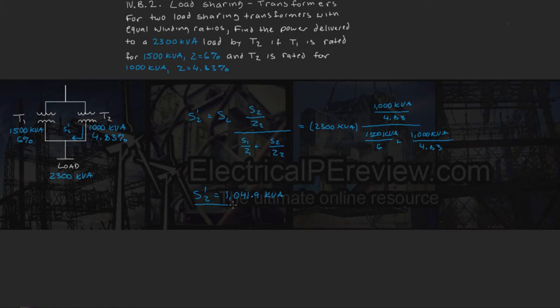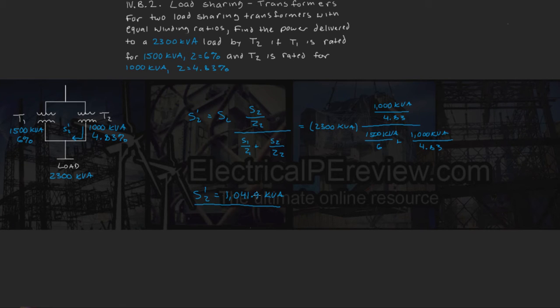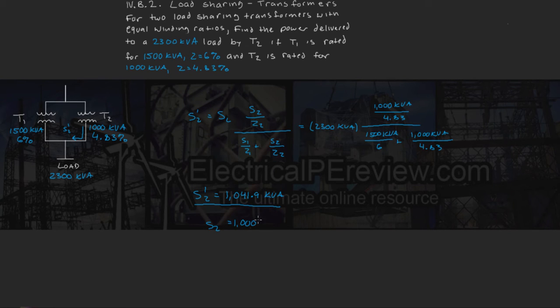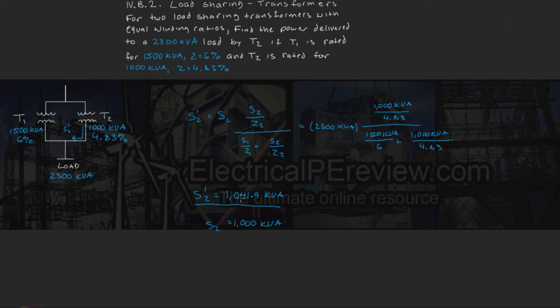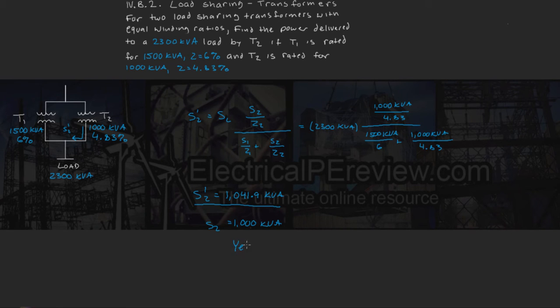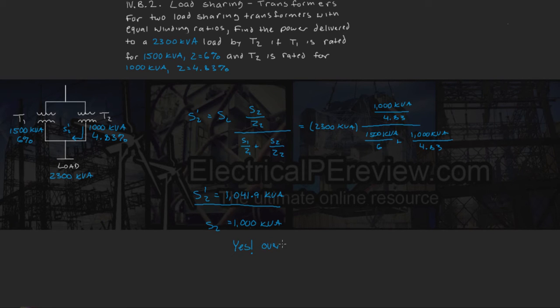Now, is transformer 2 overloaded? Well since our transformer 2 rating is only 1000 kVA, and we're currently drawing 1042 kVA, the answer is yes, this transformer is overloaded.